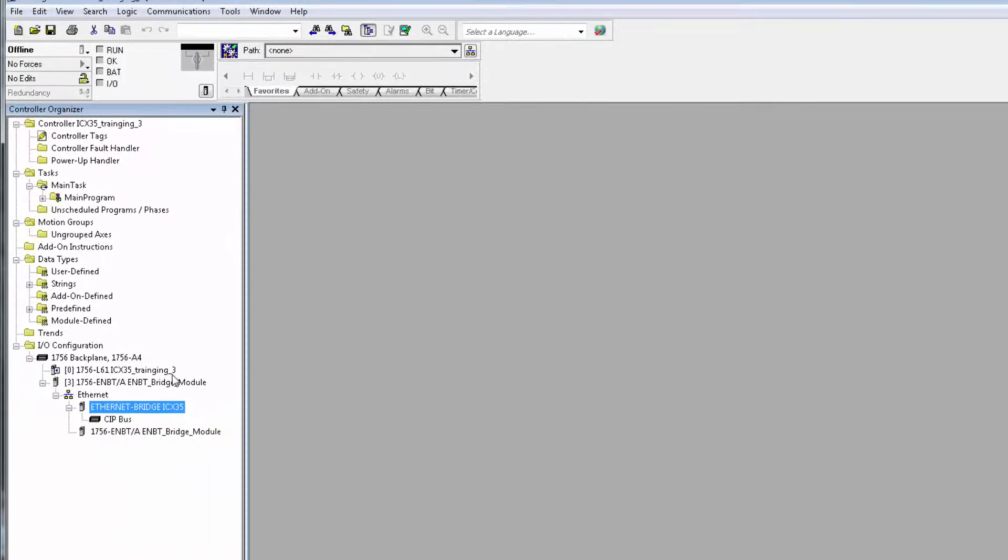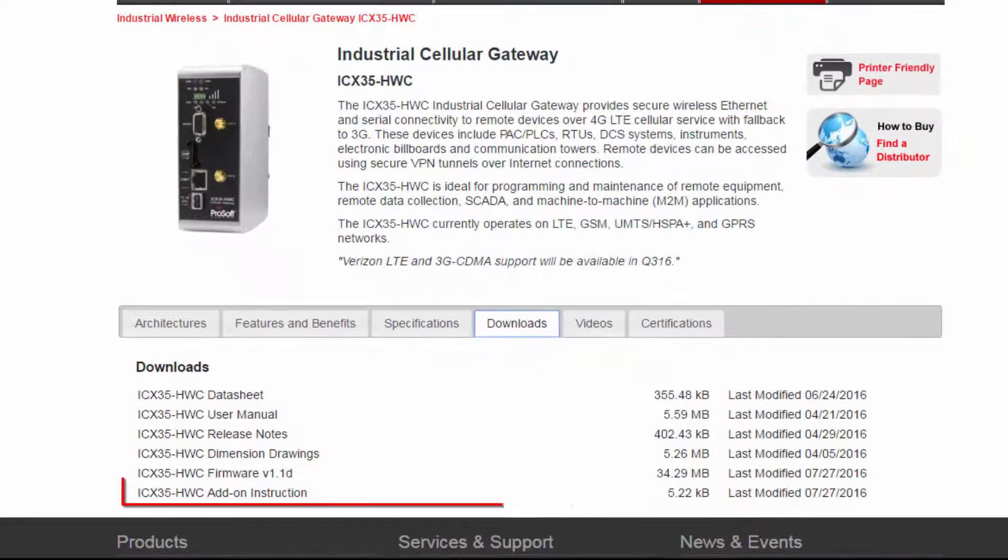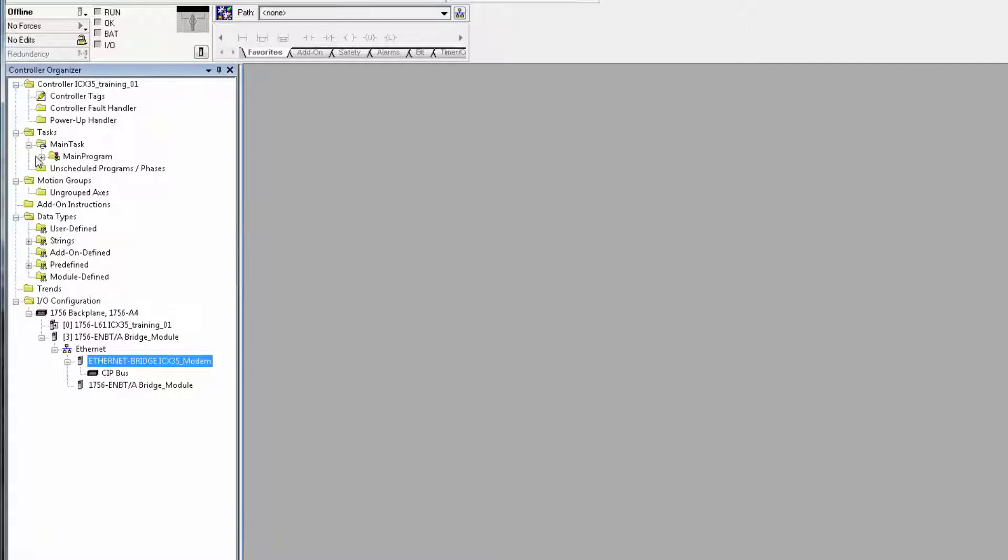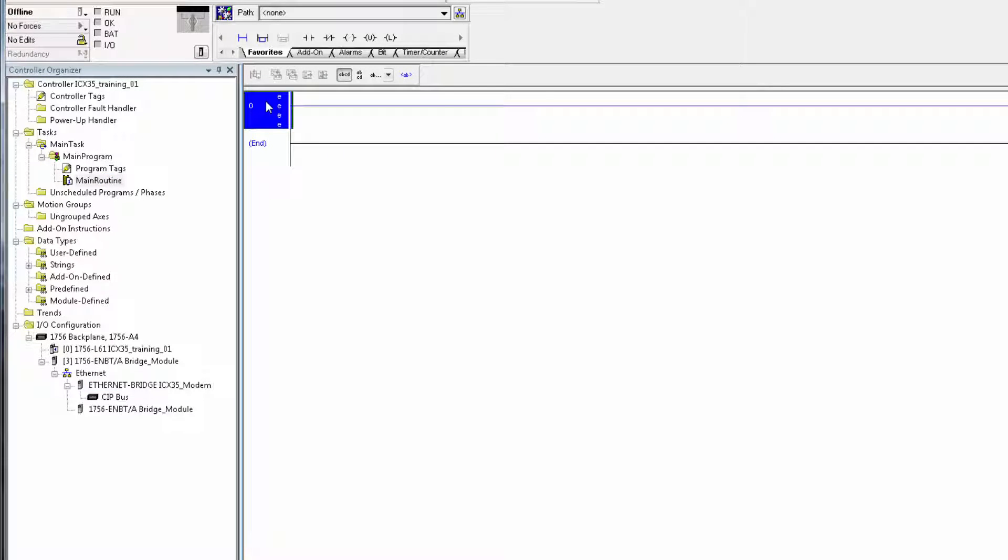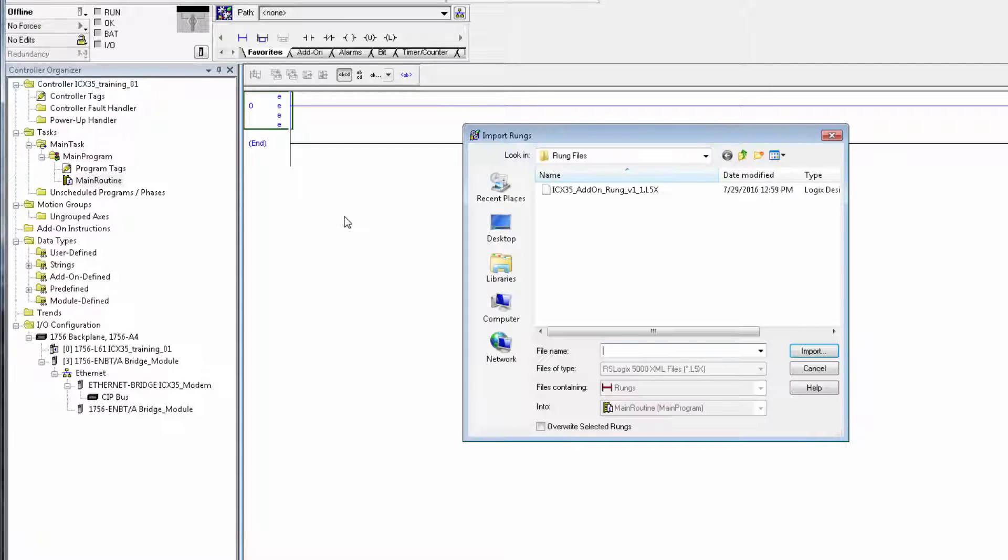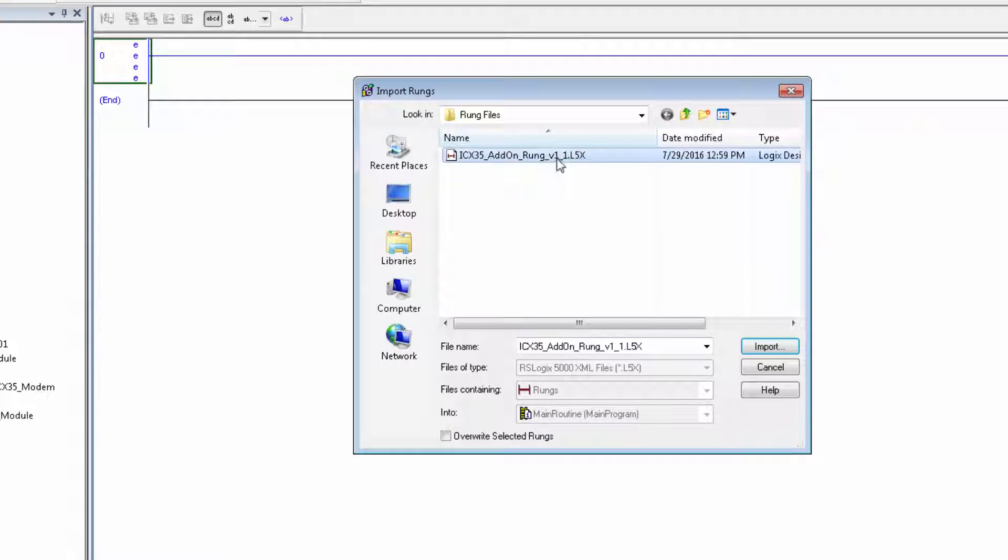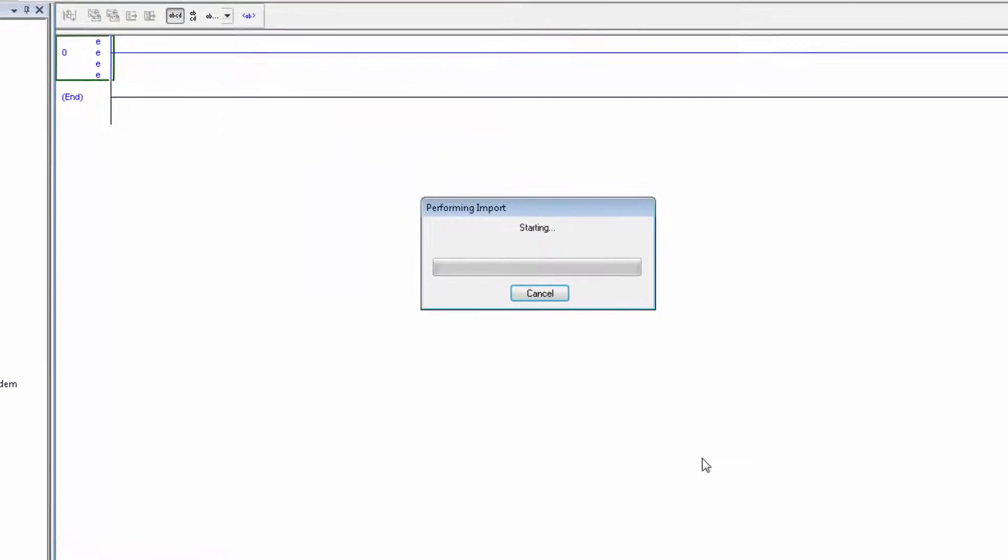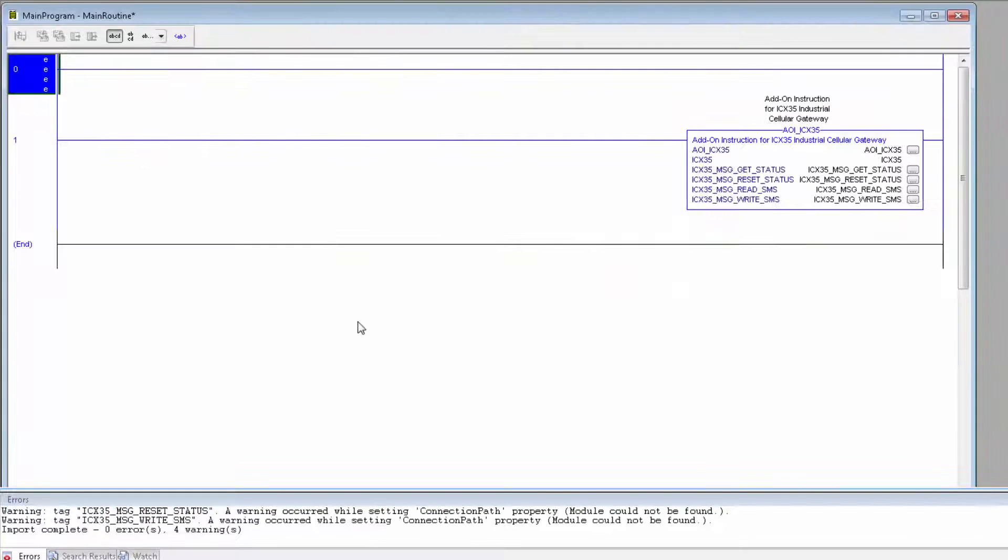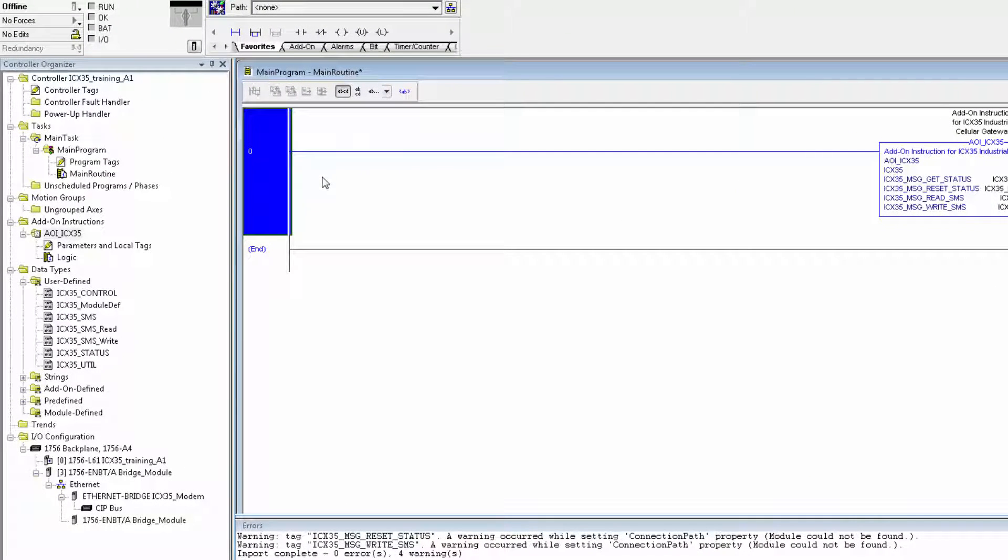Now we're ready to import the add-on instruction to our project. The AOI can be found on our product page on our website. I'll go to tasks, main task, main program, and click on main routine. Right-click on any available rung and select import rung. In the window that pops up, navigate to the location of the ICX35 add-on rung file, select it, and click import. This will open up the import dialog box, click OK, and the import process will begin. Once the process is complete, I'll delete the empty rung zero, and you can see all the new user-defined data types, as well as the add-on instruction here in the menu bar.